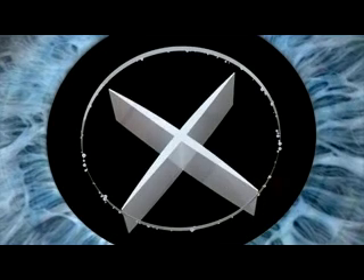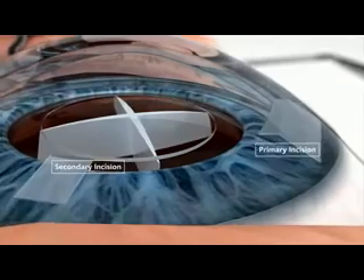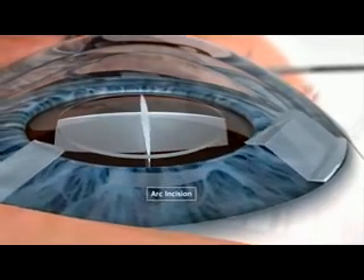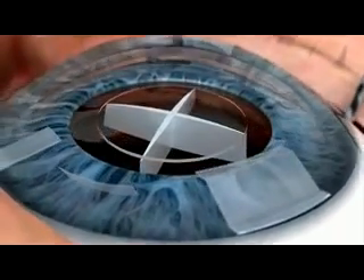Next, the lens is fragmented into easily dissected quadrants for efficient removal with reduced phaco power. Finally, the primary and secondary corneal incisions are created, as well as arcuate incisions. The laser can even perform multi-plane incisions to help promote wound sealing.